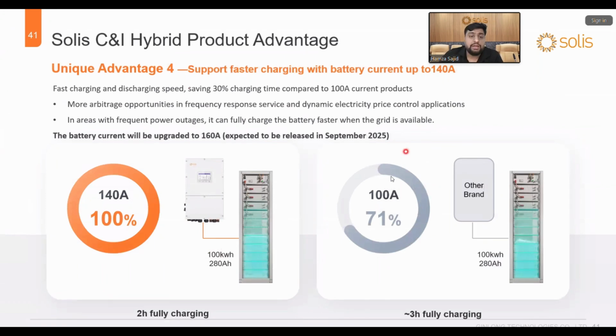Okay. Now, if we compare the charging input with another similar mainstream brand, they have a capacity of only 100 amperes. So if the system is installed somewhere where grid outages commonly happen, or the grid is available for less time, the other brand can only charge the battery up to 71%. But with the Solis inverter, as it has 140 amperes for charging the battery, it can fast charge the battery to 100%.